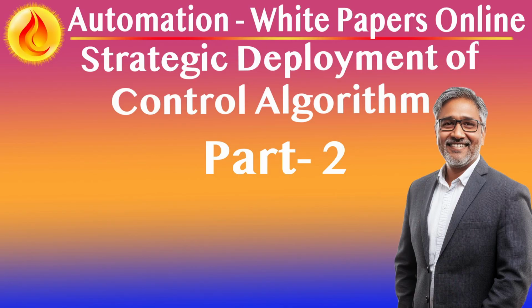How decoupling works. Decoupling adds a computational network, often based on process models or empirical relationships, that mathematically cancels out the effect of one manipulated variable on unintended controlled variables. Full decoupling cancels both cross-interaction paths in a 2x2 system, effectively making each control loop behave as a single input, single output, SISO, system. The result is true loop independence. Partial decoupling cancels only the dominant interaction path, typically from a faster loop to a slower one. This is more practical, easier to maintain, and less sensitive to modeling errors.